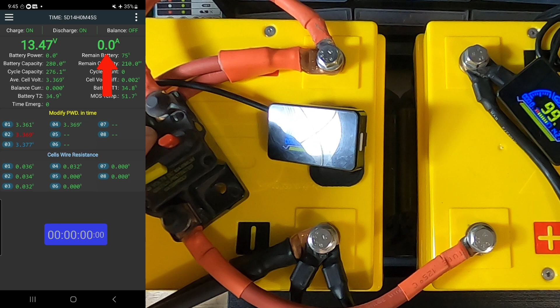Whoa, okay, it shot up. I was surprised in that break. It's not enough to trip the breaker. Remember, we have a 100 amp breaker, so we're trying to get this breaker to open up and break the circuit and protect the BMSs.